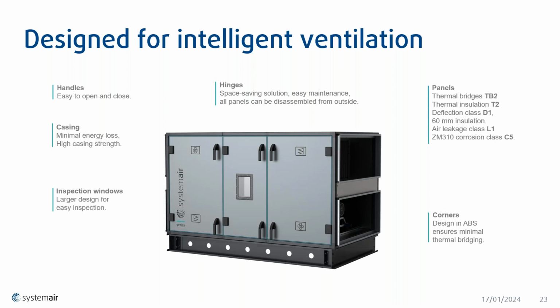So the 60 mil insulation, and one of the things to draw your attention to as well is the ZM310 corrosion class of C5. All our units are manufactured with ZM310, which is a zinc magnesium steel. It has a combination of zinc, magnesium and aluminium coating, which gets put over the actual steel. And what it does is it has a self-healing property. So if you get any scratches or anything on it, it actually self-heals the metal. We also put a fingerprint coating over it so that you get a long life. So this is the best corrosion resistance that you can get, of C5.